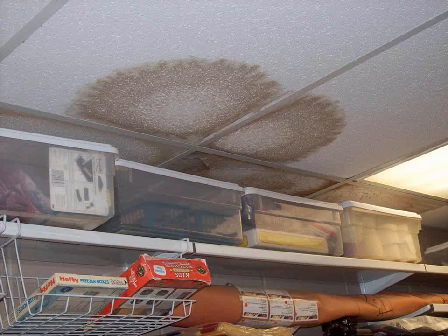And here we're going to talk a little bit about mold. Here we have some stained ceiling tiles, and it looks like it goes further back there. Question is, who knows what's growing above the ceiling tiles? It looks like it's kind of moldy from the bottom. It can only be probably worse on top where it's dark. And generally, the return plenum for the ventilation system in schools is usually right above the ceiling tiles.